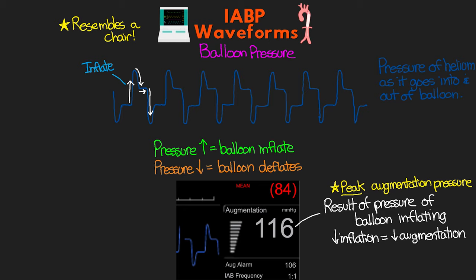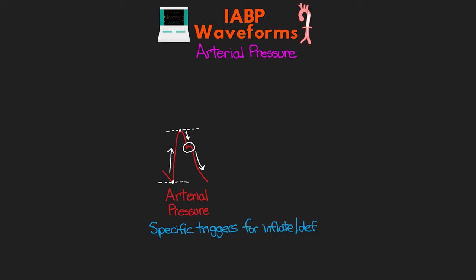The next and probably the most important waveform to pay attention to is the arterial pressure waveform. Let's talk about how the balloon pump changes our patient's waveform. Here is an example of a normal arterial pressure waveform — you can see the systolic upstroke, peak systolic pressure, systolic downstroke, dicrotic notch, and the diastolic runoff going to the end diastolic pressure. On the balloon pump, we have specific triggers for when the balloon inflates and deflates. Essentially, we want to inflate our balloon when systole ends — when the aortic valve closes. As a result of the balloon inflating in the aorta and displacing its volume of blood, we're going to see the arterial pressure increase.